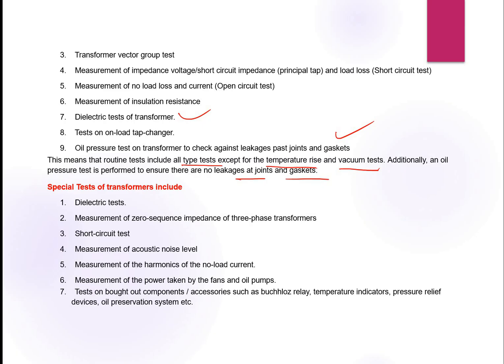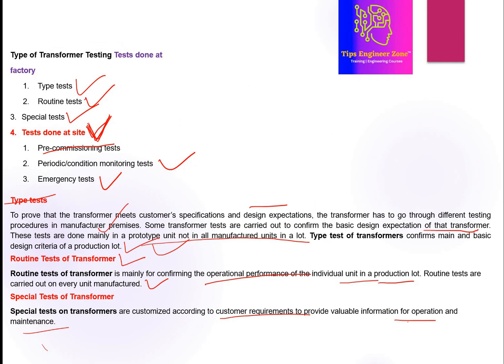Now we are going to learn about the special tests on the transformer. The special tests include some dielectric tests, zero sequence impedance of a three-phase transformer, short circuit test, measurement of acoustic noise level, measurement of harmonics of no load current, measurement of power taken by the fans and oil pumps, and tests on bought-out components and accessories such as the Buchholz relay, temperature indicator, pressure relief device, and oil preservation systems. These are all the transformer tests: type, routine, and special.